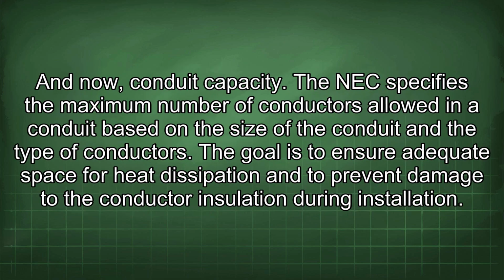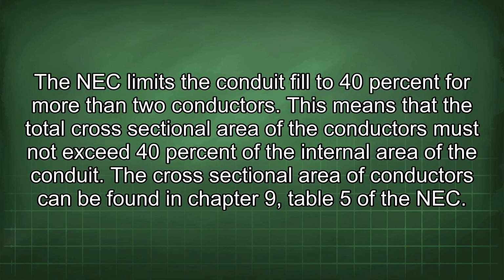And now, conduit capacity. The NEC specifies the maximum number of conductors allowed in a conduit based on the size of the conduit and the type of conductors. The goal is to ensure adequate space for heat dissipation and to prevent damage to the conductor insulation during installation. The NEC limits the conduit fill to 40% for more than 2 conductors. This means that the total cross-sectional area of the conductors must not exceed 40% of the internal area of the conduit. The cross-sectional area of conductors can be found in Chapter 9, Table 5 of the NEC.